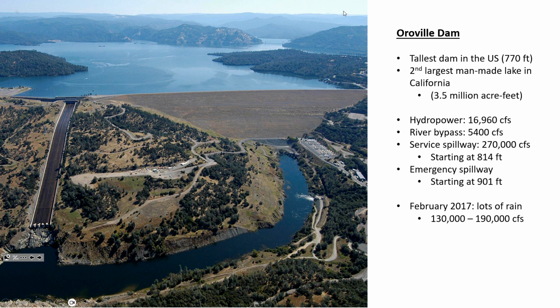And so their priority, when there's water that needs to be released from the dam, is to first send the water through the hydropower plant, and it can take up to a flow of 16,960 cubic feet per second. There's also a bypass that doesn't go through the hydropower system and not the spillway, just a secondary bypass that has about 5,000 CFS of capacity.